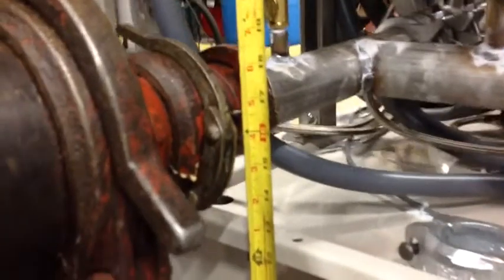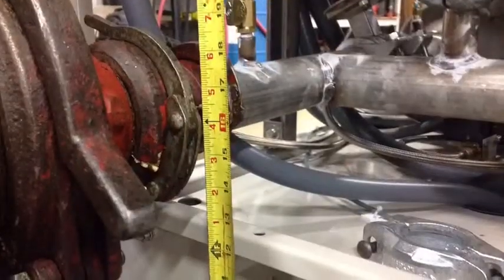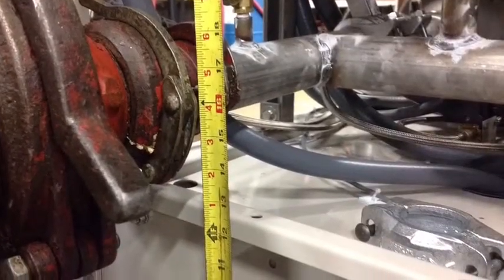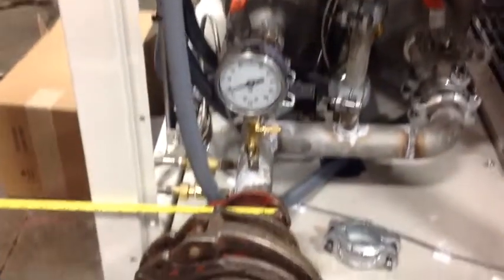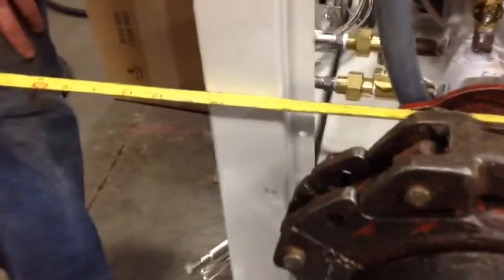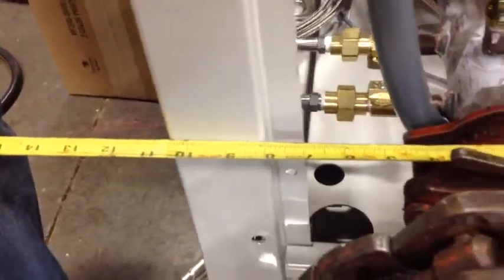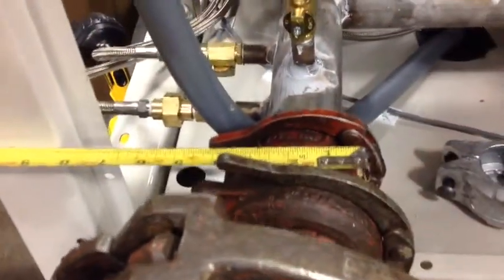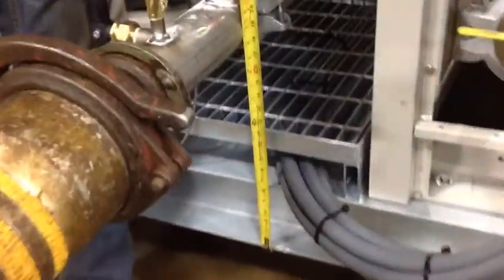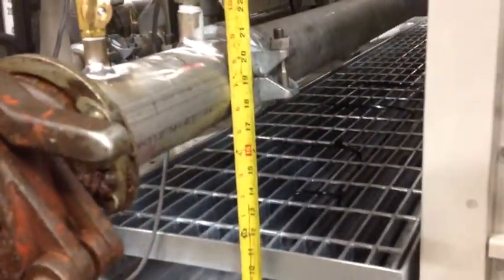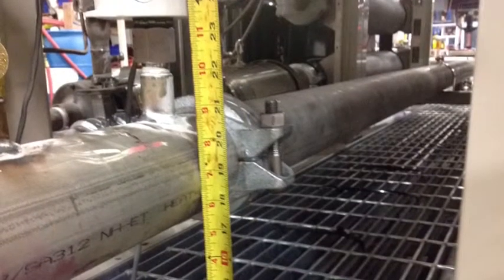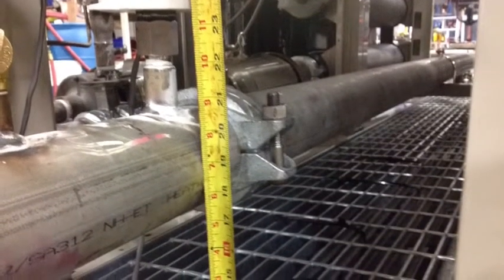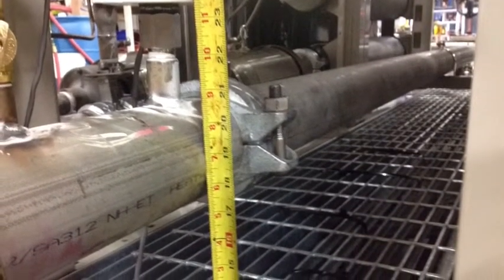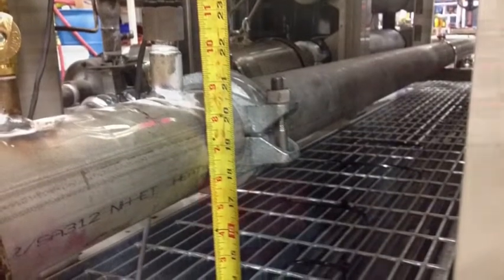So now just some measurement pictures. This is the entering connection at the pumps. This is distance above the bottom of our 6-inch lifting frame. And this is just a horizontal representation from you about 10.5 inches in to the far side of the piping. And then here's a height for the leaving connection, about 19 inches on center to that. It's a 3-inch connection at the leaving, and it's a 2-inch connection at the entering.